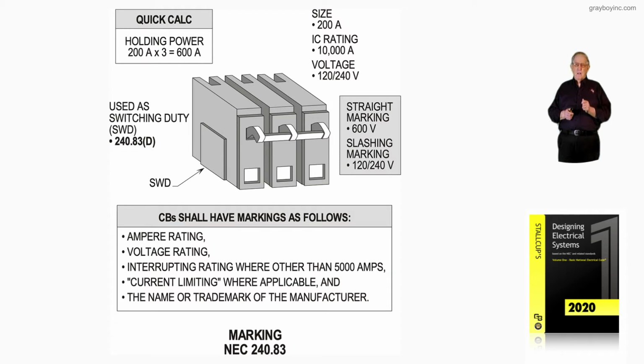But the slash marking that you see in the boxed in information to the right of that breaker, basically, kind of speaking, if it references voltage to ground, phase to phase voltage, as you see there, 120, 240, it could only be used on a solidly connected grounded system that we can read in great detail about in volume 2 of the Stallcup's electrical design book if you happen to be interested.